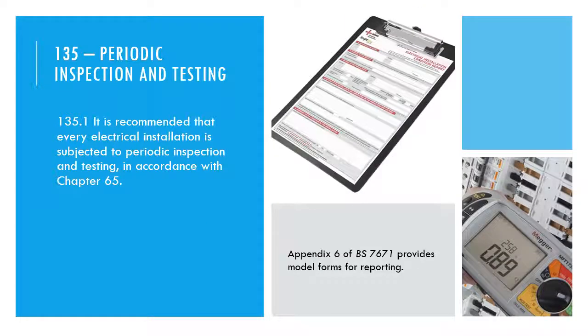And it's recommended that every electrical installation is subject to a periodic inspection. It may be running perfectly well, but there may be background underlying faults, such as insulation of cables beginning to deteriorate. By carrying out a periodic inspection and test, we can ascertain if the system is still fit for purpose.